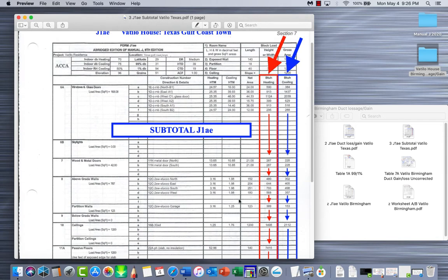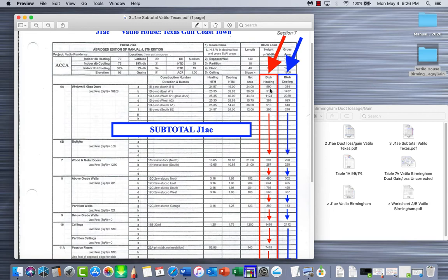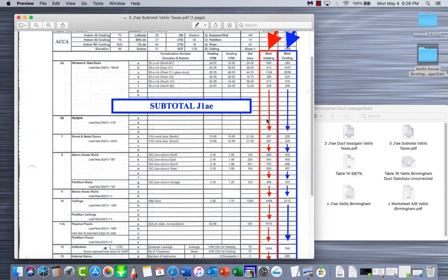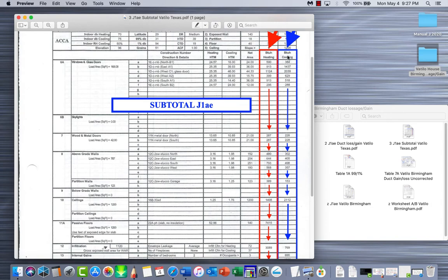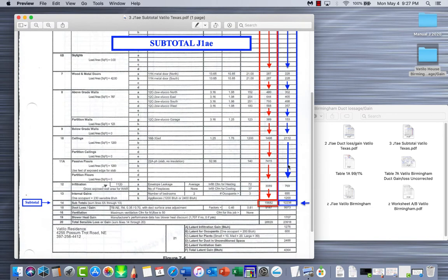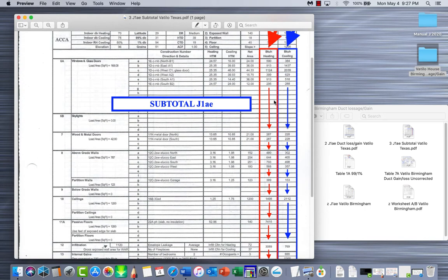Line 14 - basically you take your heating BTU per hour and add this entire column up all the way down to line 14. You can see right there they got 19,682. Then you do your cooling all the way down through here and add them all up to your subtotal. Please take your time and make sure you get everything right.